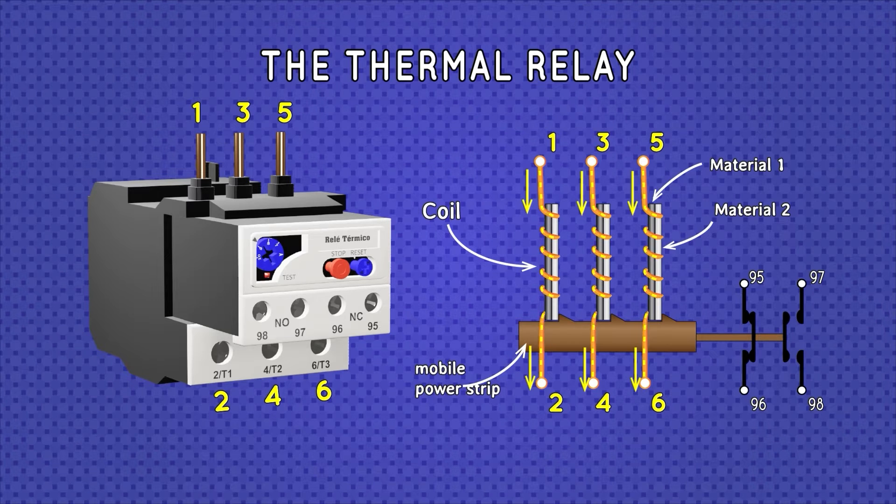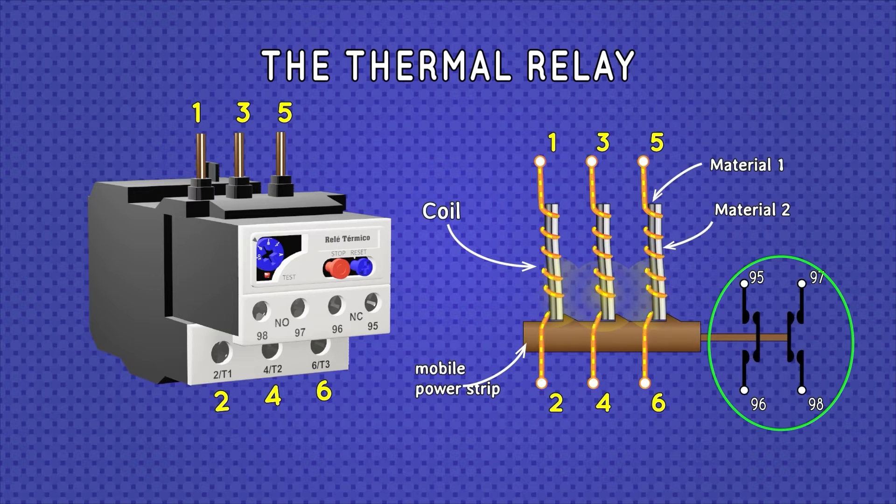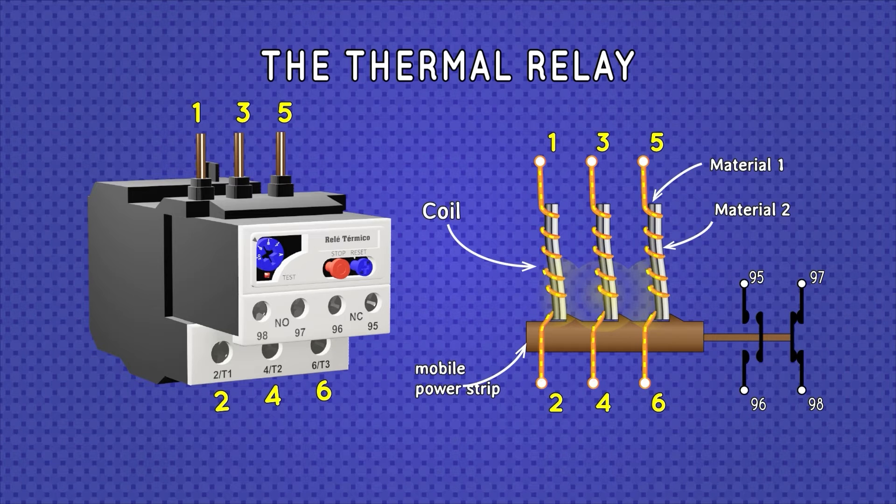By circulating current through each coil, the bimetals constantly monitor the current absorbed by the motor. If the current that circulates is higher than the adjusted one, then the bimetals heat up and deform, allowing the mobile strip to move and push the auxiliary contacts, causing them to change position and state.